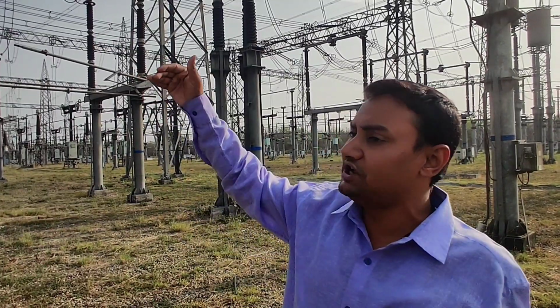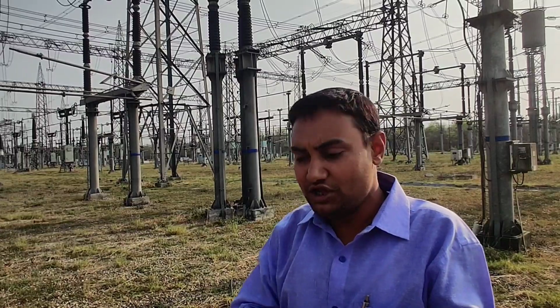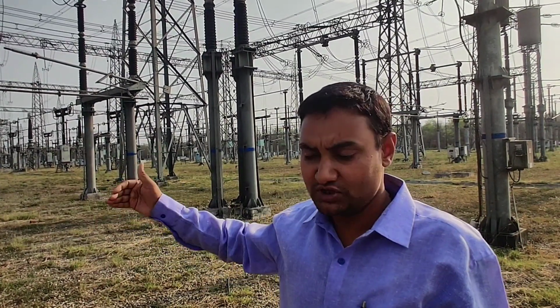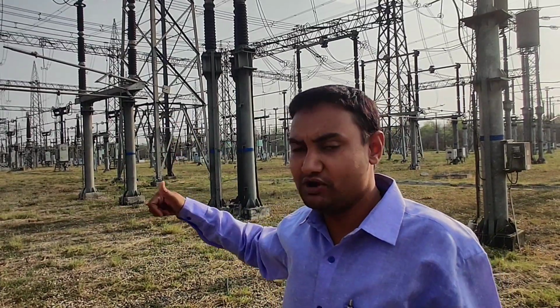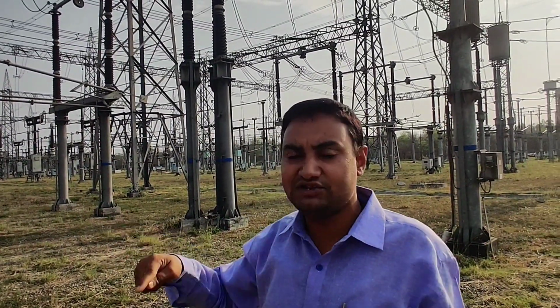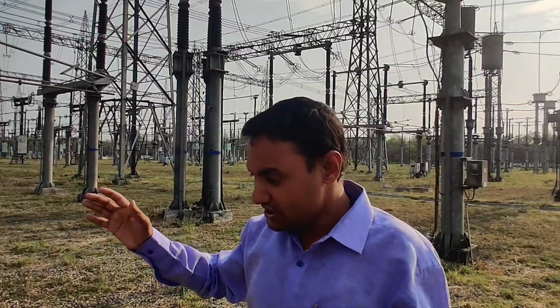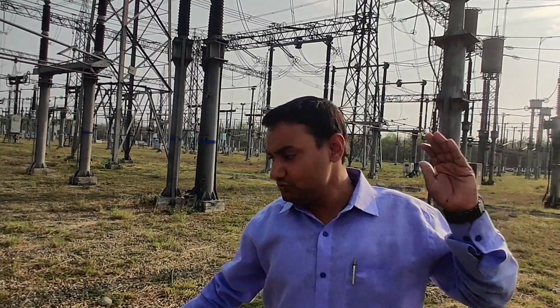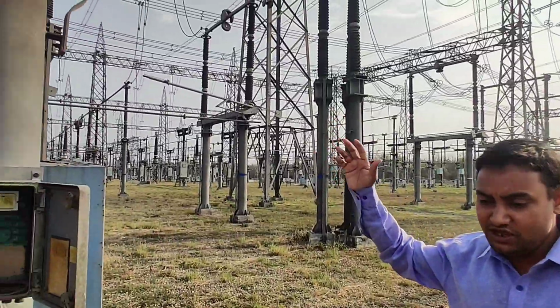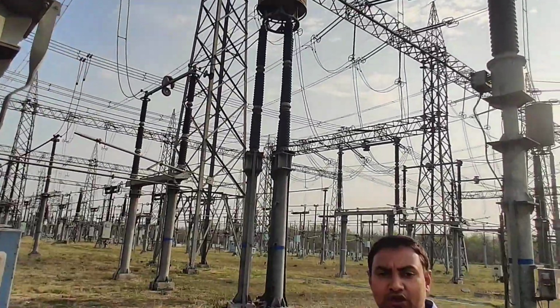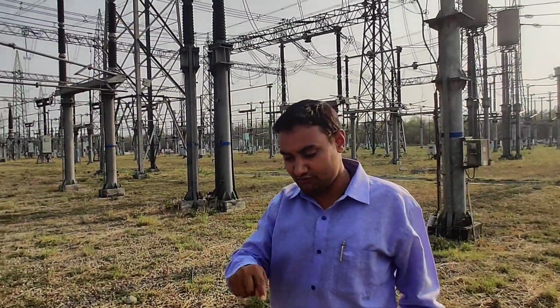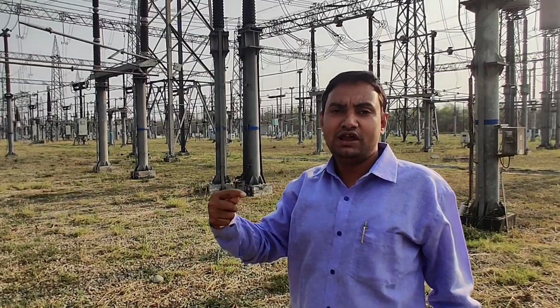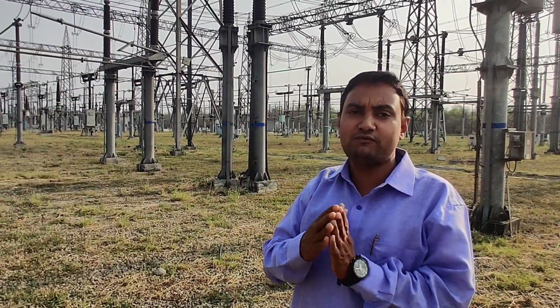That means this CVT provides you a lower impedance path for transmission of this high frequency signal to the remote end, from this local substation to the remote substation. It provides a low impedance path. Now if you see the next element, the wave trap. As its name suggests, the wave trap is used for the trapping of waves, and trapping of waves of high frequency.